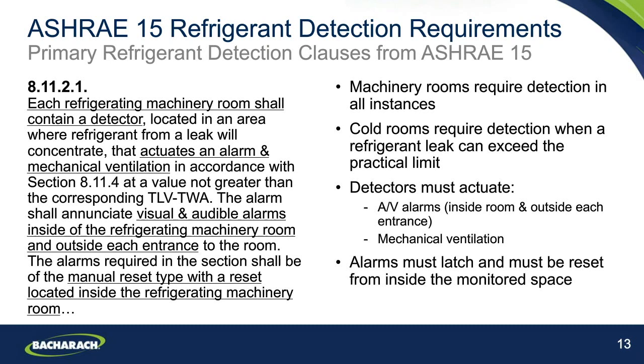So the summary points here would be that a machinery room requires detection in all instances, and cold rooms require detection when a refrigerant leak could exceed the practical limit or the refrigerant concentration limit within that space. And the detectors must actuate the audio-visual alarms inside and outside each entrance to the room, and must actuate mechanical ventilation in the room. And we can note from the last part of this clause that the alarms must latch and they must be able to be reset from inside the monitored space.